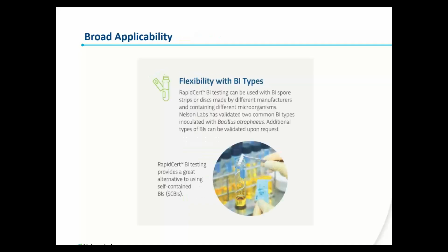The second is that there is broad applicability for this validation that's already been performed. As I mentioned, we did already validate for different manufacturers of BIs. We have the ability to validate for additional BI manufacturers if that's something that's needed to support your particular process. And we are also able to validate for different organisms. So if we're looking at something like the need for a geobacillus, that's something that is possible.